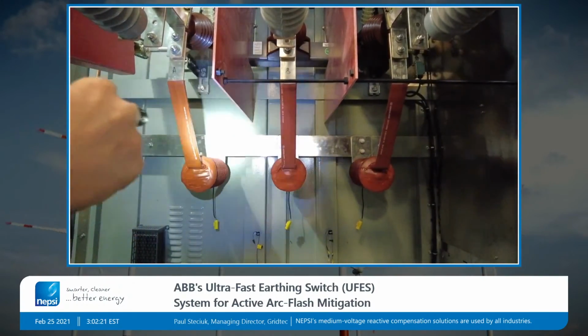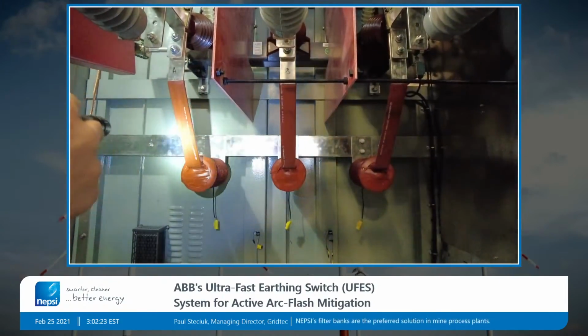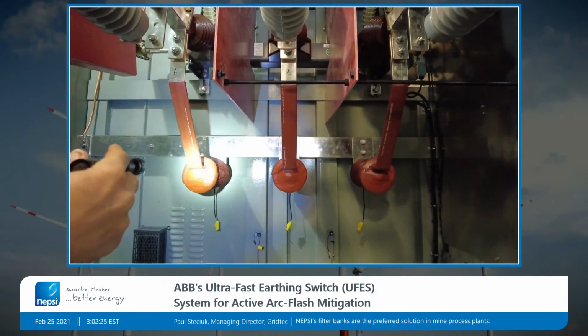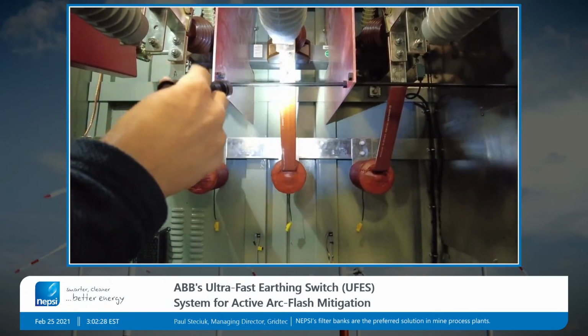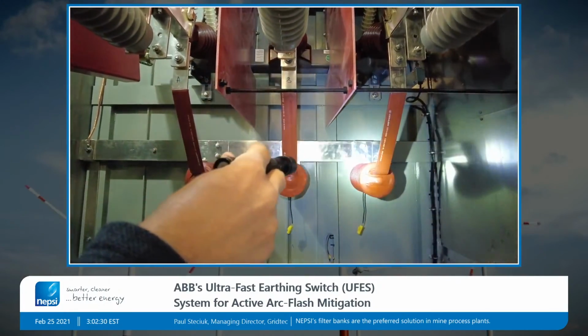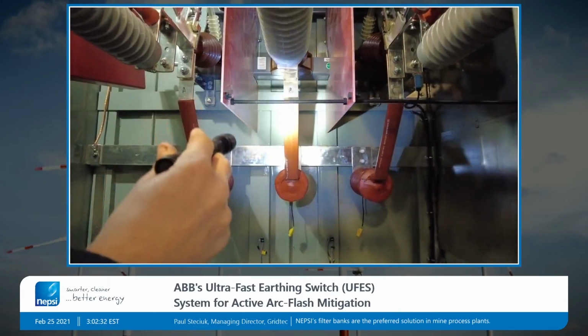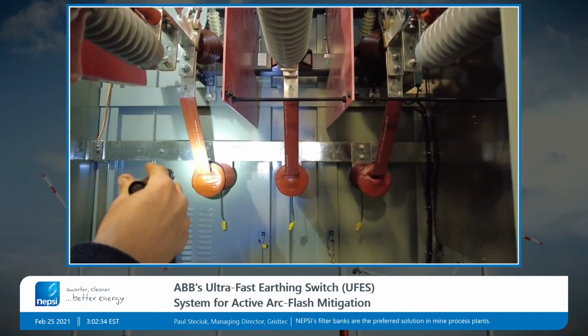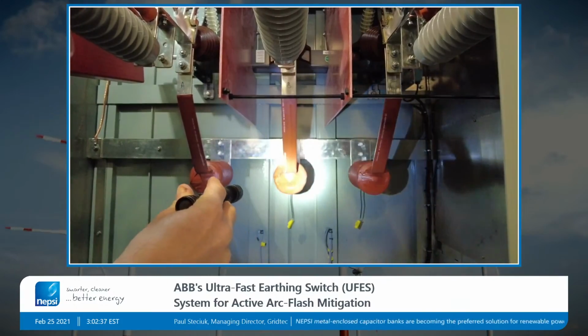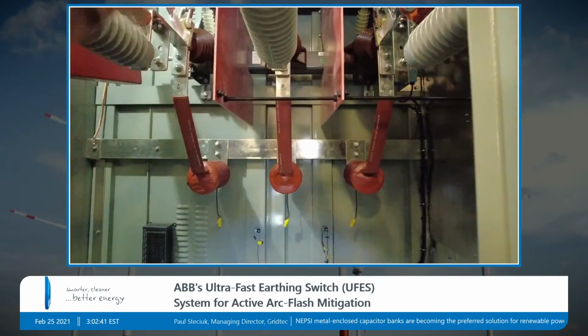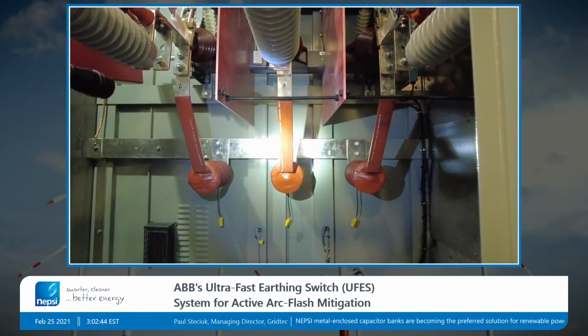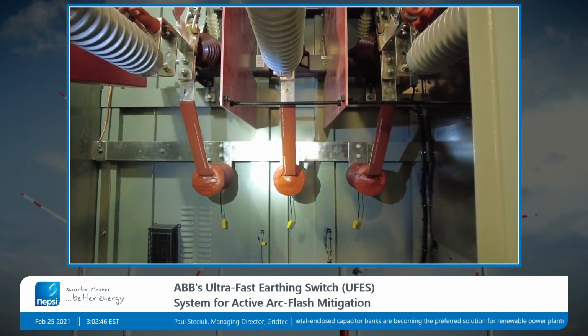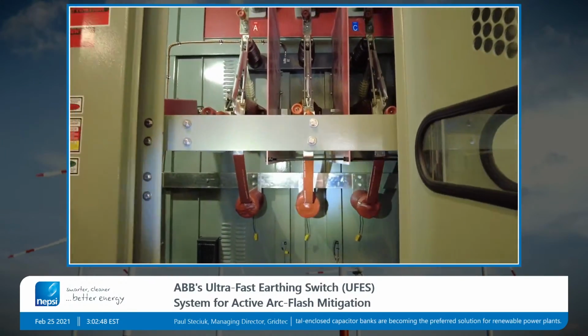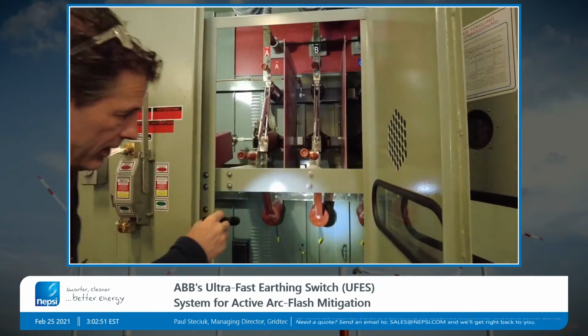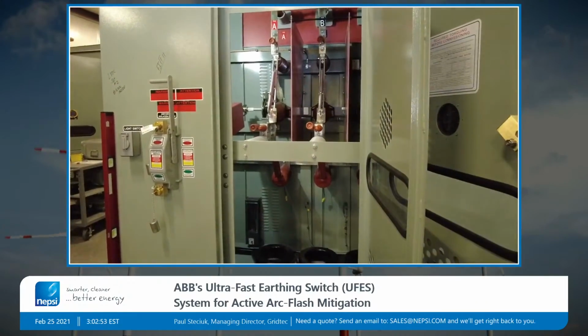On the back side, there's a large ground bus that will ground the fault current, and on the high side, that's connected directly to the source cables. We have our primary side for the switching elements, and so if a fault is detected, the internal of this bottle will basically short out like a switch to the ground bus, and it'll extinguish any arc that takes place.